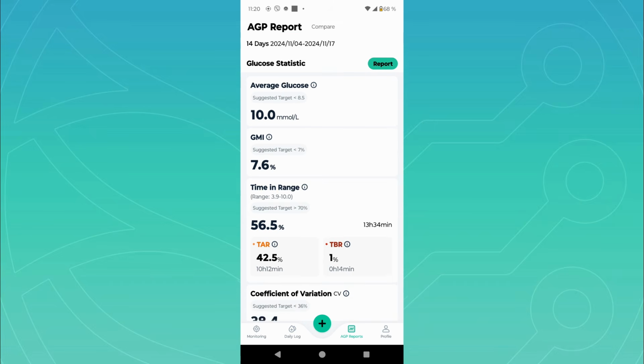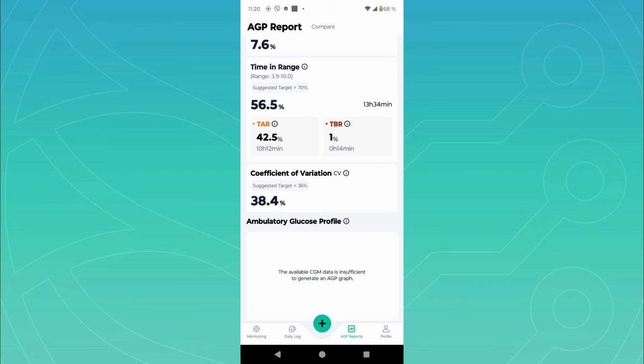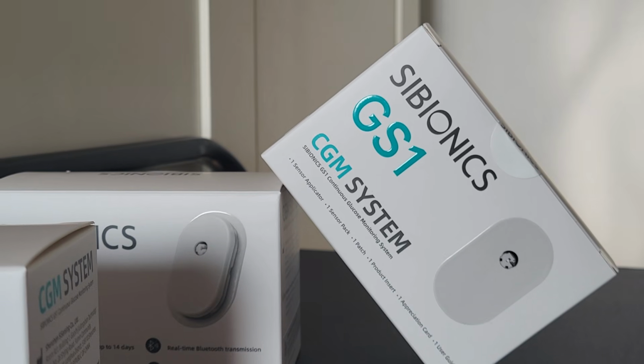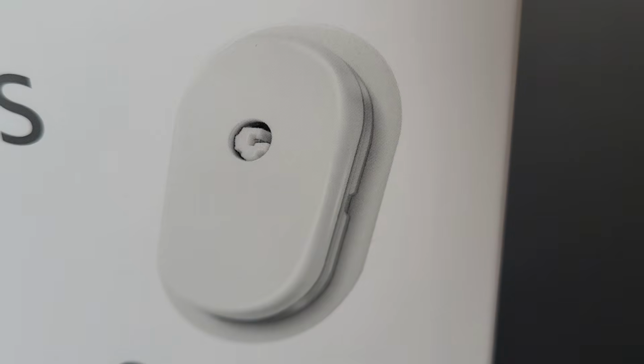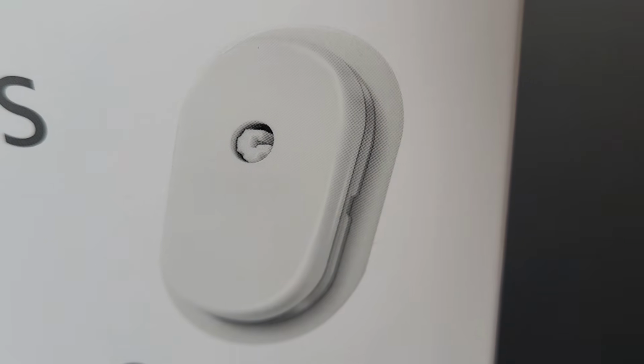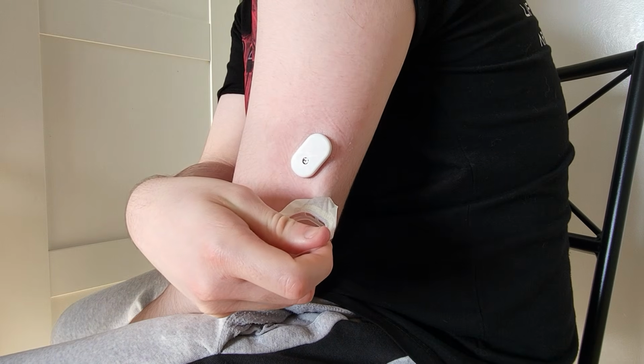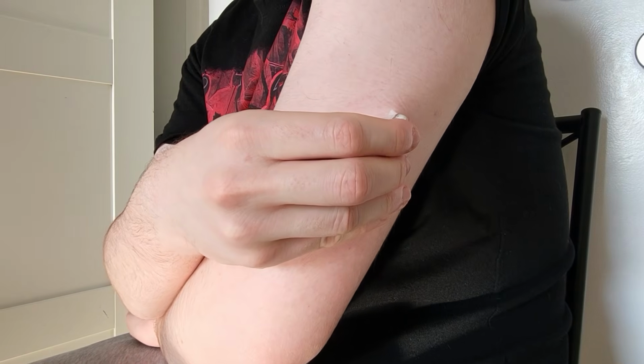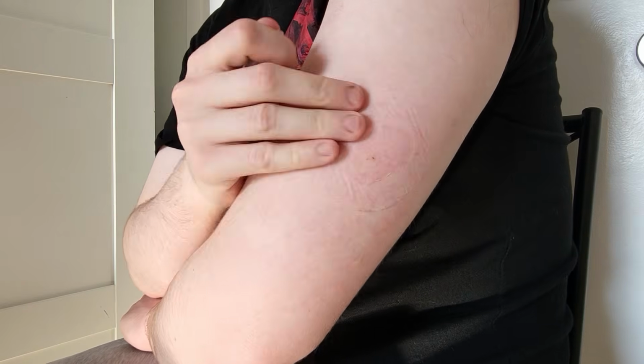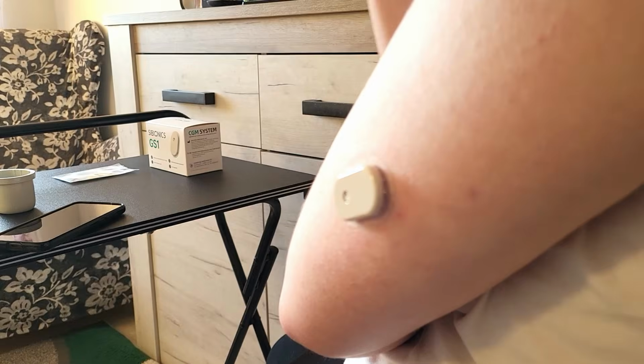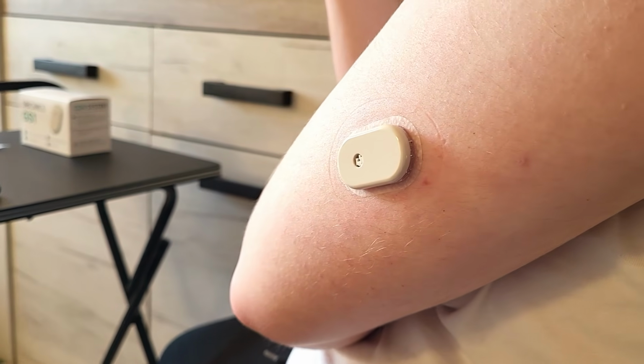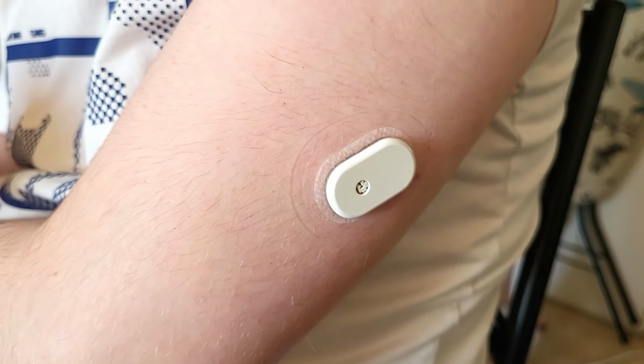Please note that the sensor will stop working after 14 days and must be replaced using the same procedure. It will also be important to remove the sensor if you notice irritation or discomfort at the application site. We do this by peeling off the overpatch from the sensor and then removing the sensor. You should dispose of the used overpatch and sensor properly and apply a new sensor if needed.